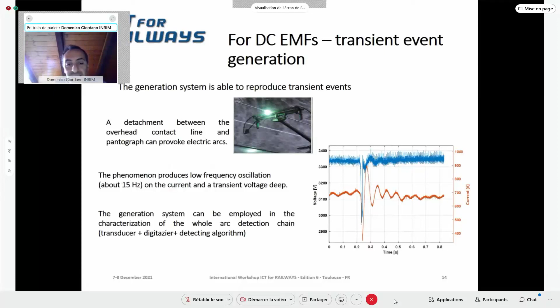...we can use this generation setup to characterize new possible functionality of the energy measurement function. In fact, one idea is to integrate in the energy measurement function other functionalities than energy measurement, for example, functionalities that perform power quality monitoring. By exploiting the communication between the energy measurement system on board and on ground, it is possible to collect power quality indexes in order to perform, for example, predictive maintenance.